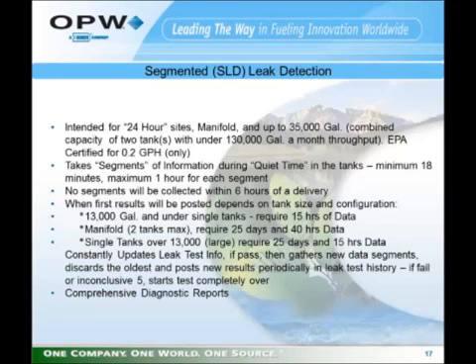When the SLD function is first started up in a unit, the first test results will be posted depending upon several conditions. For a standard tank under 13,000 gallons, single tank, it requires a minimum of 15 hours of data to be able to declare the first test result. For manifold tanks or large tanks, it requires a minimum of 2 conditions. The first condition for manifold tanks is 25 days, and over that 25-day period, it must collect at least 40 hours of data. For a single tank over 13,000 gallons, it requires, again, 25 days, but over the 25 days, 15 hours of data. It will constantly update the database with new data.